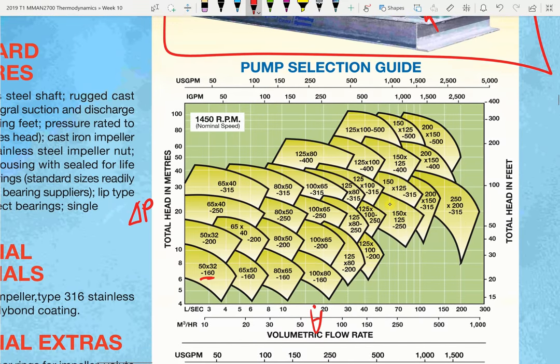We can use litres per second, or metres cubed per hour as the hydraulic schematic uses. This pump can do about 4.5 litres per second at maximum flow rate, or if run at very low flow rate, produce a maximum of about 11 metres of head, which is a measure of ΔP.